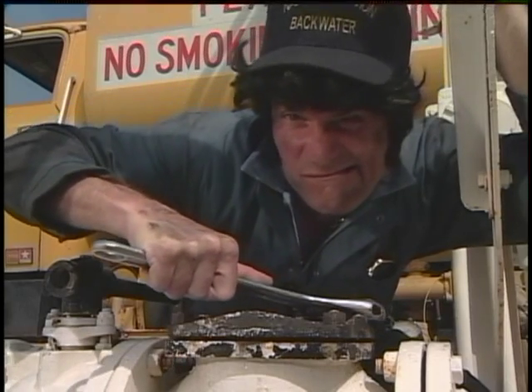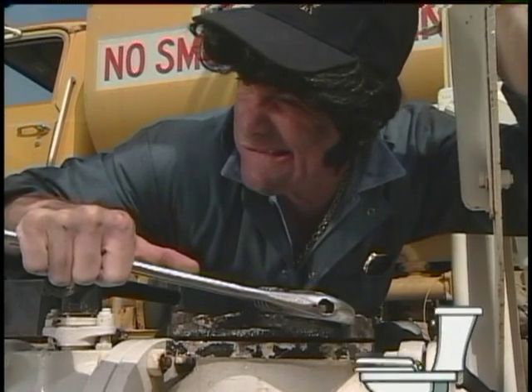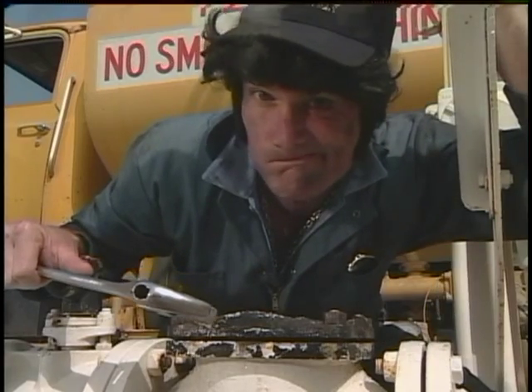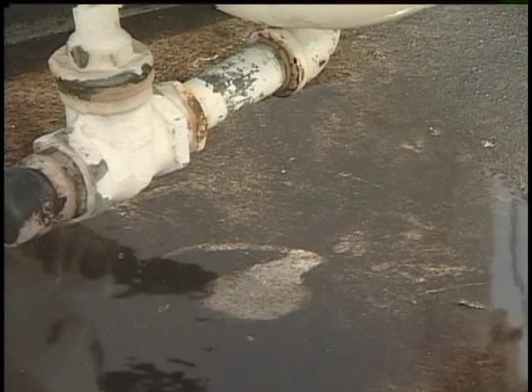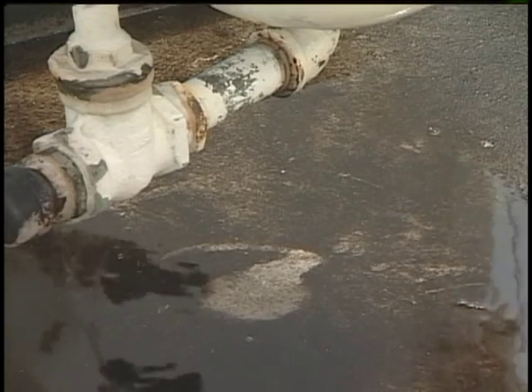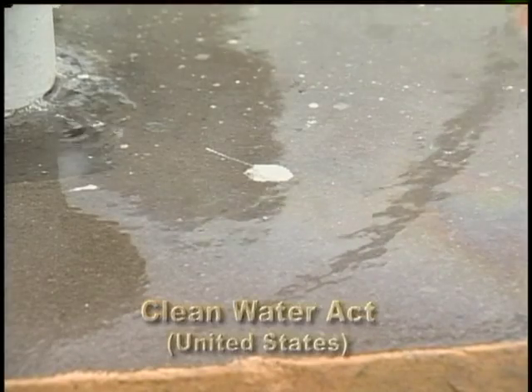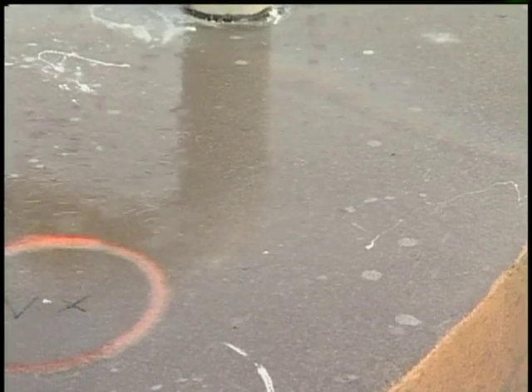Some people think the government gets its fuel for free. Right now we're paying about a dollar a gallon, so that's hundreds of dollars a year for one little drip. Elvis has thoughtfully provided a drip pan where it'll evaporate, causing air pollution. And this tank does have secondary containment, but when it rains, that drip pan will immediately develop a sheen — it only takes one drop. When the shallow pan overflows during a rain, there'll be a sheen on all the water in the secondary containment, meaning Elvis can't release it without causing a knowing violation of the Clean Water Act, or overseas, the final governing standards for that country.